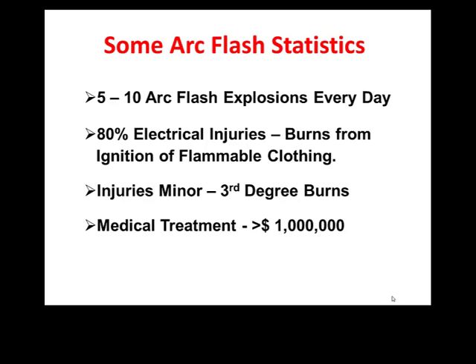There are 3 work-related deaths each week due to electrocution, which would include arc flash fatalities. The extent of the injury depends on the amount of short-circuit energy available and the reaction time for the overcurrent protection device, such as a circuit breaker or fuse. Reaction time can be from milliseconds to seconds, depending on the type and condition of the overcurrent protection device used. A serious arc flash injury requiring treatment at a burn center can result in medical costs exceeding $1 million.